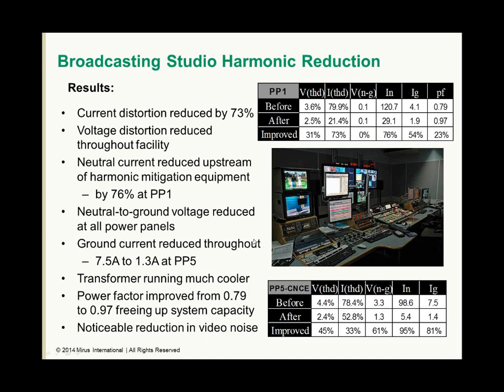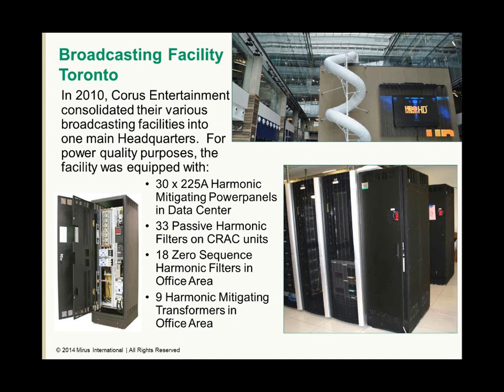At the headquarters of a large broadcasting facility in Toronto, computer room power panels equipped with the electromagnetic devices were installed throughout, as well as linear passive harmonic filters for the computer room air conditioners and harmonic mitigating transformers throughout the office area.